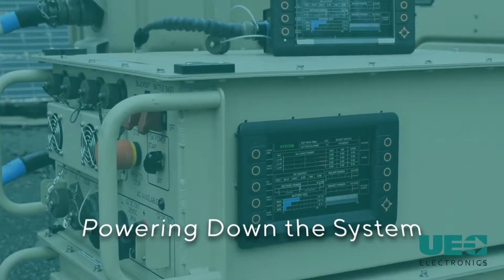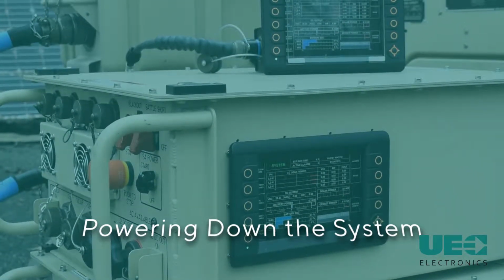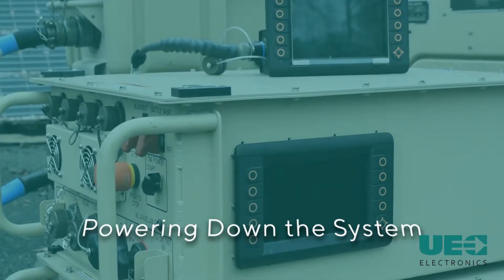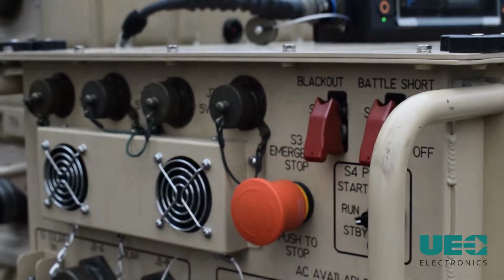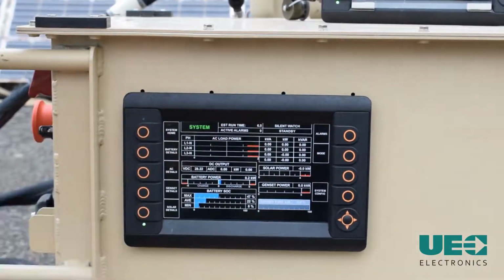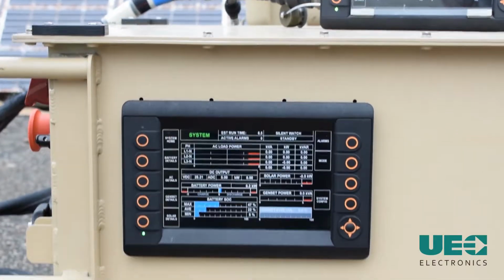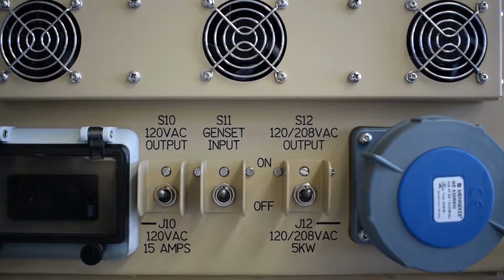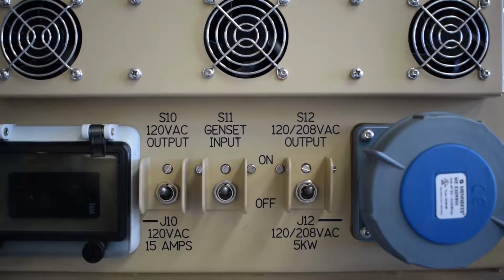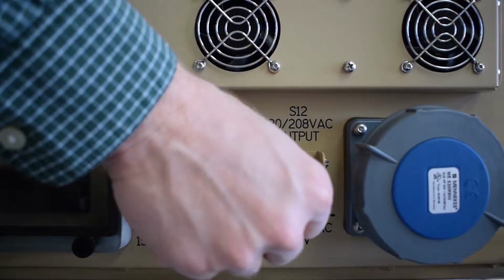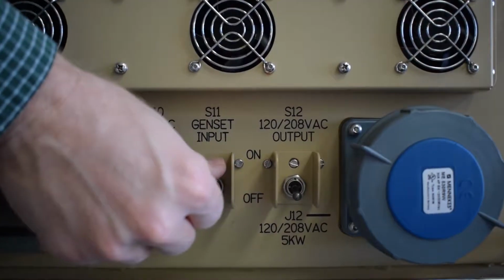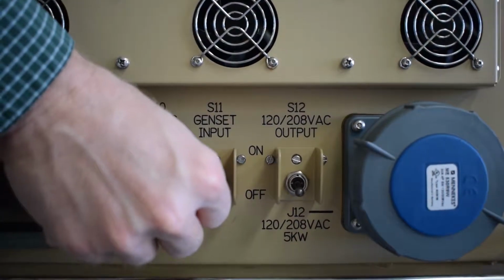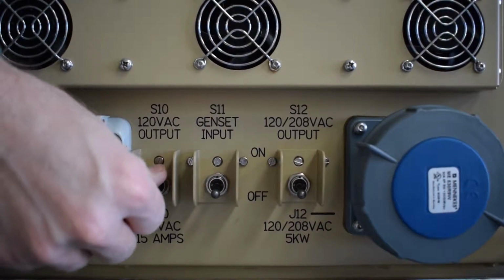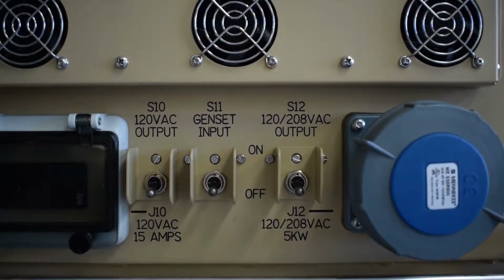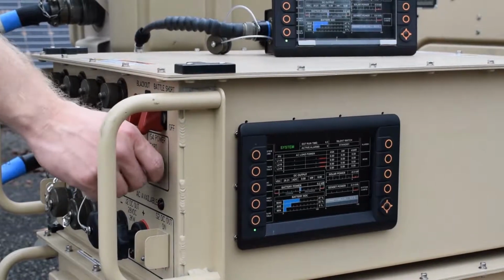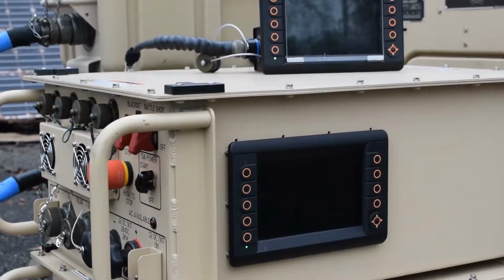Powering down the system. The following steps should be taken to safely power down the MEHPS system. Number 1. Rotate the S4 power switch on the DC PDU to the standby position. Turn off the S10 120 volt output convenience outlet breaker, the S12 AC output load circuit breaker, and the S11 genset input circuit breakers on the AC PDU. Rotate the S4 power switch on the DC PDU to the off position.